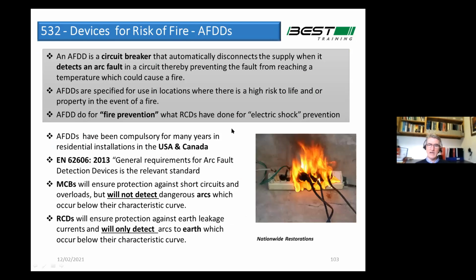Arc fault detection devices. I've shown this image here. I have no idea if that is a fire due to arc fault, but it gets the message home. This is what happens with loose connections and breakdown in insulation. Over time, you get a generation of heat due to the loose connection or the breakdown in insulation. Small currents start to leak, or current tries to jump across an air gap due to a loose connection. It causes ionization of the air, which results in heat buildup, which results in the insulation starting to burn, develops into carbon, then more tracking, etc. It's just a vicious cycle, and eventually it builds up and starts a fire. So for that reason, they're now recommending AFDDs be used in certain installations where there's a risk of loss of life and so on, that we mentioned earlier in chapter 4.